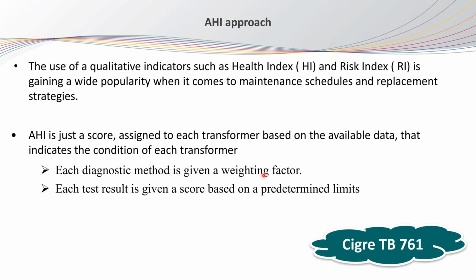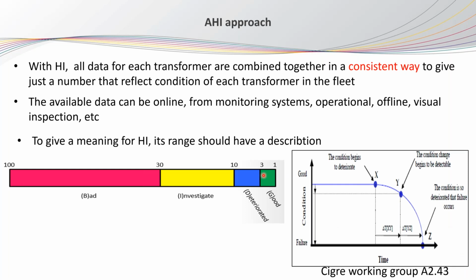There are other methods, of course, that we will see also in the coming slides. For more details on the health index method, one of the useful documents in this aspect is the CIGRE Technical Brochure 761, and it discusses in detail the different classical methods of the health index approach. So the health index is a method that will enable you to evaluate the condition of the asset in a consistent way by applying the same rule. The available data can be online, offline, operational, or from visual inspection. One of the things that is quite important is to give a meaning to the value of the health index. So if you have a health index of 2 or a value of 10 or 30 or 50, what do these values mean?